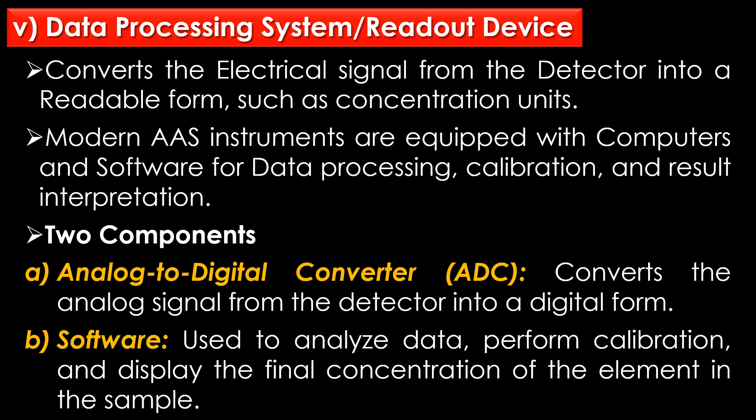The fifth part is the data processing system or readout device. It converts the electrical signal from the detector into a readable form such as concentration units. Modern AAS instruments are equipped with computers and software for data processing, calibration, and result interpretation. There are two components: the analog-to-digital converter (ADC), which converts the analog signal from the detector into digital form, and the software, which is used to analyze data, perform calibration, and display the final concentration of the element in the sample.